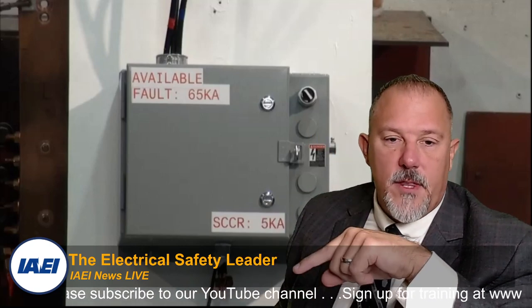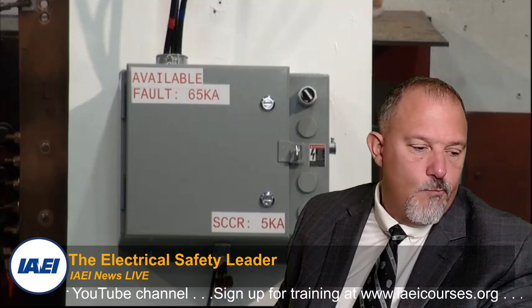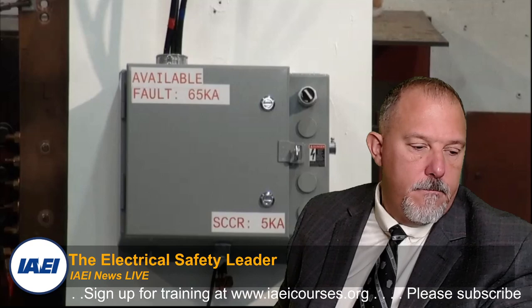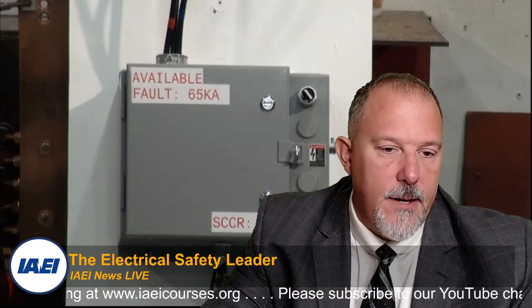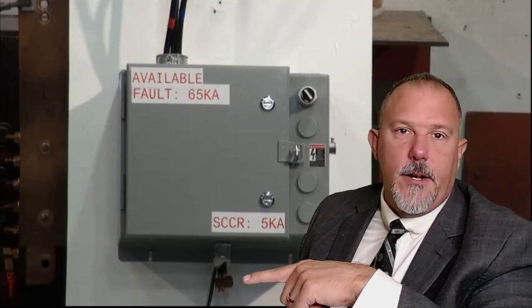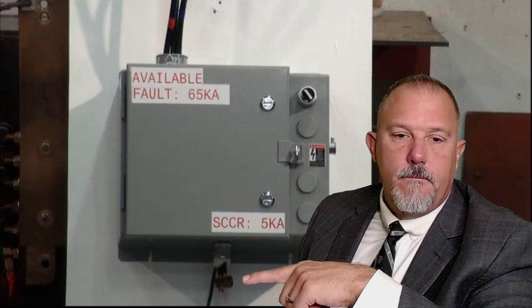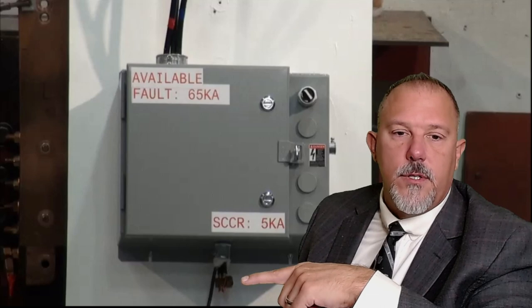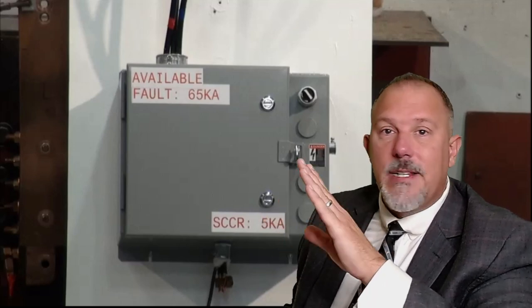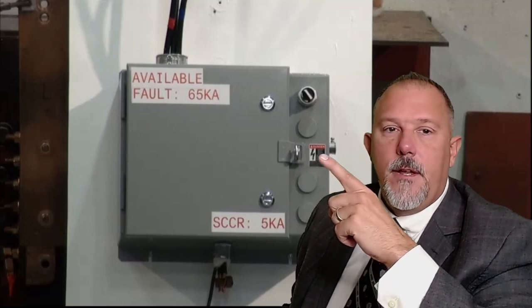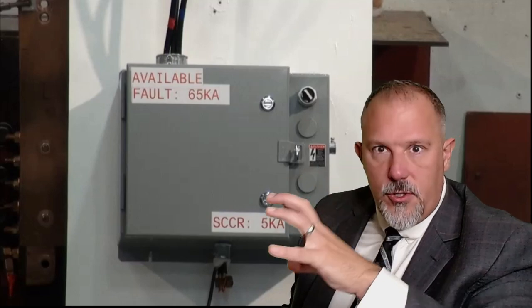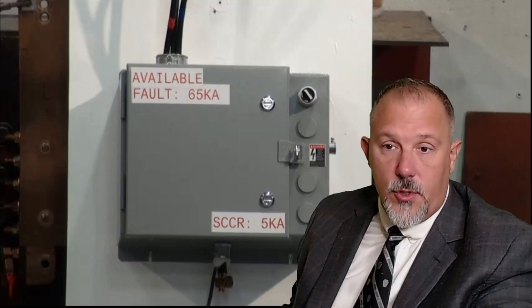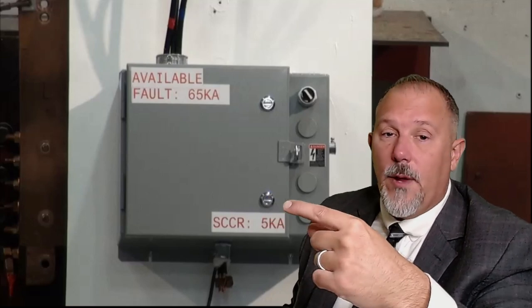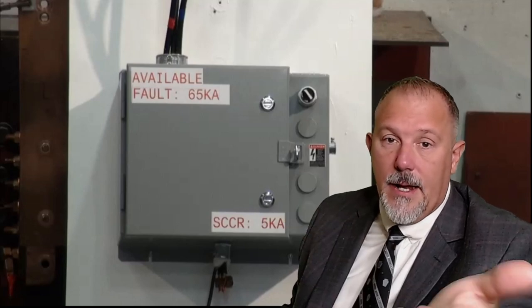The fault is not inside this equipment. The fault is right down here on the bottom. Let's take that out one second. You see there's a lug right here, and that's a split bolt that's basically terminating, creating a bolted fault on the secondary of this. So what's happening is fault current is simply passing through this equipment. This equipment is supposed to be able to withstand that pressure via its short circuit current rating. But as you know, when I misapply a product, I get, unfortunately, an unintended rapid disassembly in the field. This is what happens.